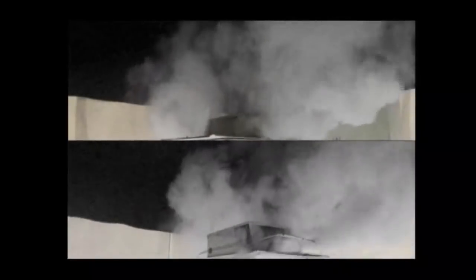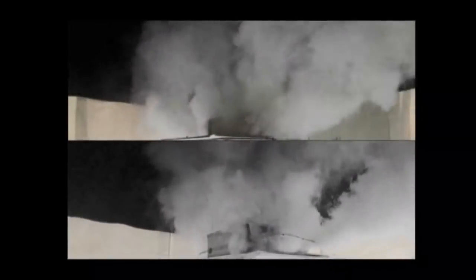Anytime the video slows down, you know it's going to get interesting. So we see another cell level failure. You start to see the off-gassing, and you start to see some sparking from the opening in the box. This is starting to raise the concern: will this gas ignite, and what would be the result of this ignition?